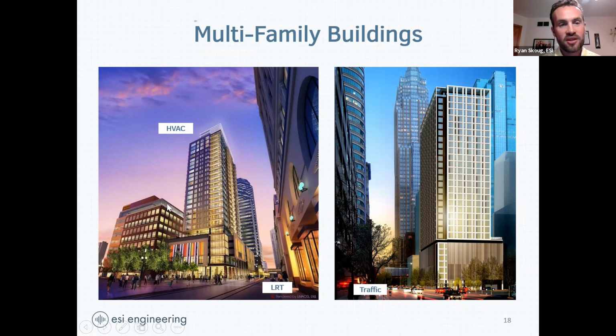Actually, it's kind of funny. This was another one of our projects where they've got this giant penthouse air handling unit, and people at the Nick on 5th were complaining about the penthouse noise coming over. So we had to do noise monitoring on a balcony, figure out that yeah, they are exceeding the code requirement, and then we engineered some silencers to go on top of these units to reduce the condenser fan noise, because the condenser fan is pulling air through coils for cooling used by the systems, and the condenser fans are just slapping the air. They're not really engineered to be silent by any means, so we had to engineer some silencers to go on top of these units that wouldn't exceed the static pressure requirements, because those condenser fans aren't very efficient and don't pull air very clean and neat. You can't put a silencer on there that would make it so they can't pull air anymore, because they can't handle that. So it had to be a pretty open system to block some noise, and we were able to get them below the code requirement there. So that was kind of an interesting one.